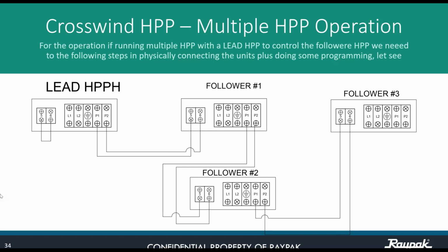The value of the code will be flashing, so the number 1 is going to be flashing, and the modification code 1 is water temperature control through terminals P1 and P2, exactly like it is shown on the diagram. Press the fan pad to confirm and quit the modification code. Press the power pad to exit. The follower heat pumps also need to have the water set point at 104. Press and hold the lock pad for 3 seconds to light up the screen, unlock, and press the plus pad to raise the set point to 104.